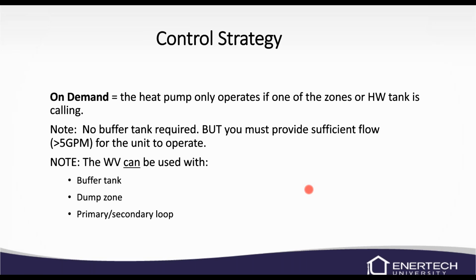Control strategies. There's a couple different ways you can do it. The way that we would recommend is basically on demand, which is the heat pump only operates if one of the zones or the hot water tank is calling. With the TurboMax tank and the variable speed, we don't have a buffer tank. So there's no real need to heat up a tank and leave it when the unit can handle it, as long as we've got flow, that we can run the unit only when a zone is calling. So we're not storing water. We're just producing the hot water when we need it.